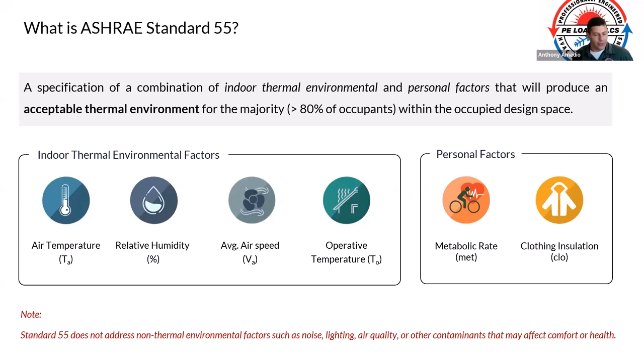Basically what ASHRAE Standard 55 is, it's a specification of a combination of indoor thermal environmental factors. We're talking air temperature, relative humidity, average airspeed, operative temperature, similar to a mean radiant temperature. And it's also a combination of personal factors, what you're wearing, what you're doing, that's going to produce an acceptable thermal environment for the majority of folks in the occupied space. They say more than 80% is the majority. I kind of say 80% or more in case you're on that threshold. Standard 55, just so you know, we're talking thermal comfort. We're not talking about non-thermal factors like noise, lighting, air quality, odors, stuff like that.